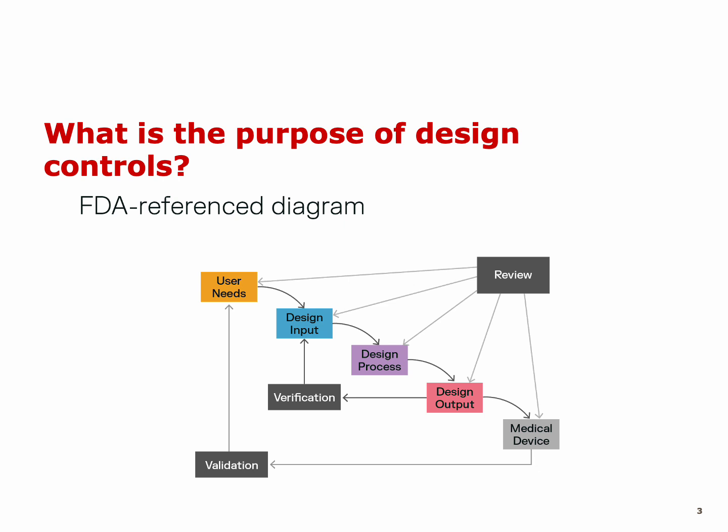And of course, once the medical device is on the market, we will still have to do the validations and reviewing the plan and reviewing the design for the input, the process, and the output, because the medical device may not be 100% safe, it may not be 100% accurate. We may have new technologies that are going to make the function of that medical device much better, improving that. So as long as your medical device is on the market, it's also the text of the law that you have to go through the validations and to look into reviewing the design of your medical device, which is on the market.